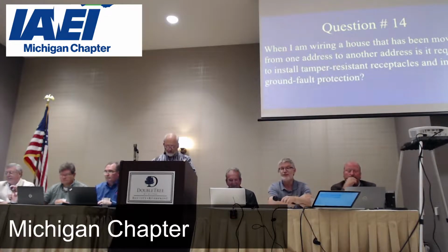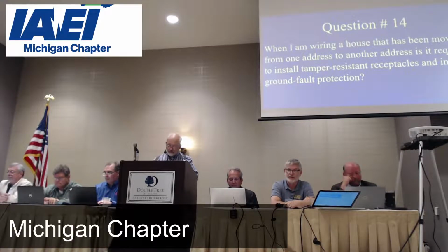Okay, Dan. When I'm wiring a house that has been moved from one address to another address, is it required to install tamper-resistant receptacles and install ground fault protection? This is one of those inadequate questions, because it says when I am wiring, what does that mean, you're wiring the house? If that means you're running all new circuits in there when the house gets to its new location, replacing receptacles and luminaires, then yes, you need to bring that up to the current code.